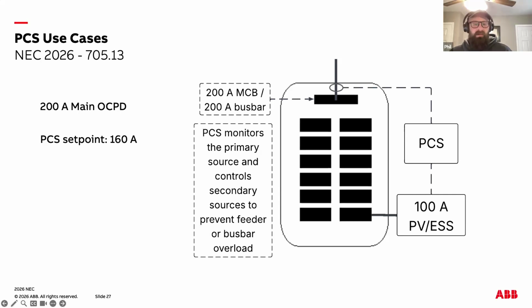Because the PCS continuously supervises the current flowing through the service conductors and bus, it can automatically reduce PV and ESS output, curtail loads, or take other control actions to keep the total current within the equipment's rating. This capability means you can interconnect more generation or storage capacity than 705.12 would normally allow, without replacing the panel or upsizing the service. The PCS provides the safety margin by guaranteeing that the combined current from all sources and loads never exceeds the busbar or conductor ampacity.